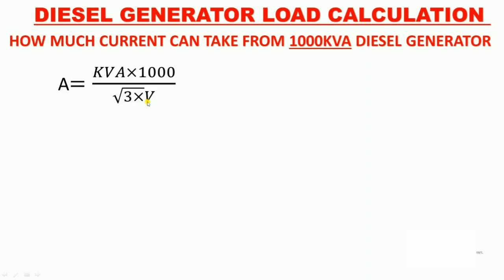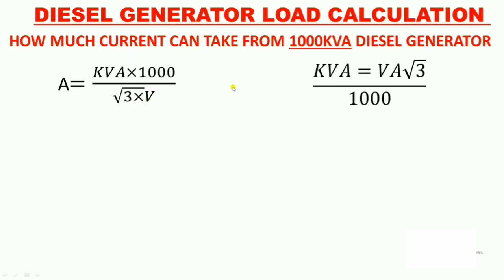First understand how this formula is derived. To derive this formula we need to understand kVA. VA is equal to V × A, and for kVA we divide by 1000, for three-phase supply we include √3. From this, kVA × 1000 cross-multiplied gives us amperes, with V and √3 in the denominator portion.